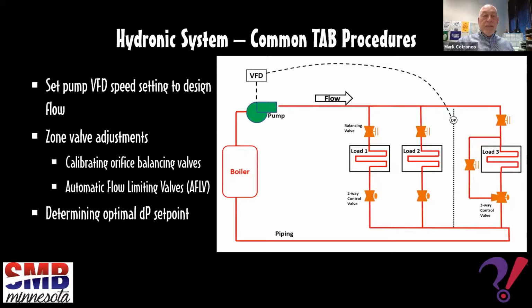After all the balancing valves are measured and set, enough control valves are indexed full open to match the design flow of the pump. And the BAS display is monitored and the differential pressure set point reset down until only one or two valves are 100% open and maintain room set point. The final set point is then documented in the report. All right.